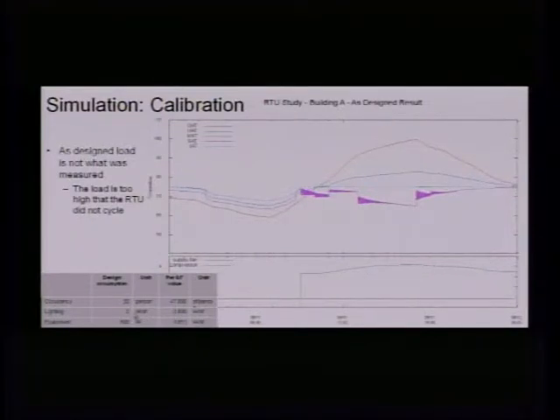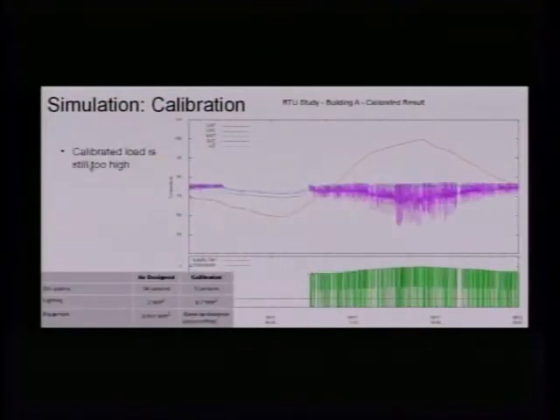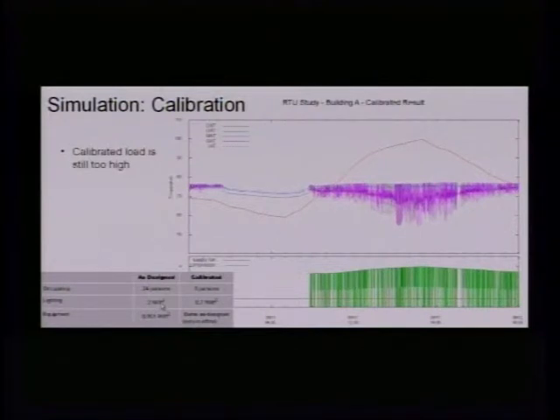Now mind you, we're talking about lighting of 2 watts per square foot, which is way too high. So this is not what we measure. We know it has to cycle. So what I did was to calibrate the load. We changed the load according to what was there during the measurement. We counted the people at the time of the measurement. The design says 24, so we change it to 6. And for the lighting, we put 0.7. That's what we estimated was there. And the equipment as designed, but only in the office, in a small portion of the zones.